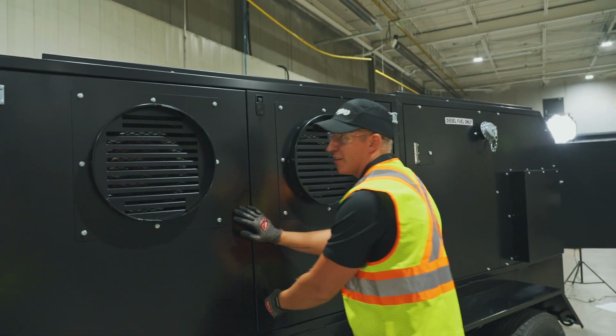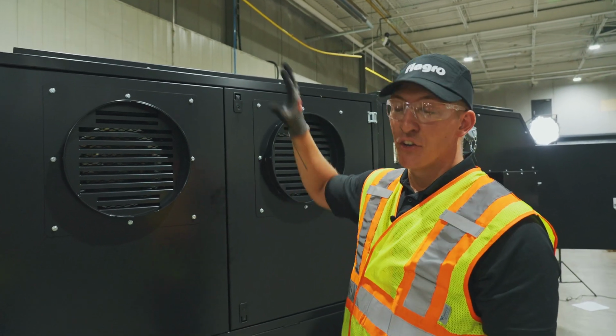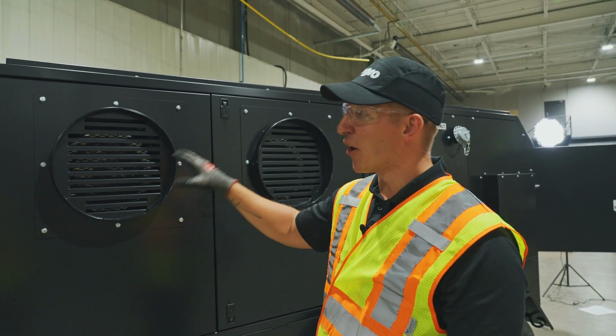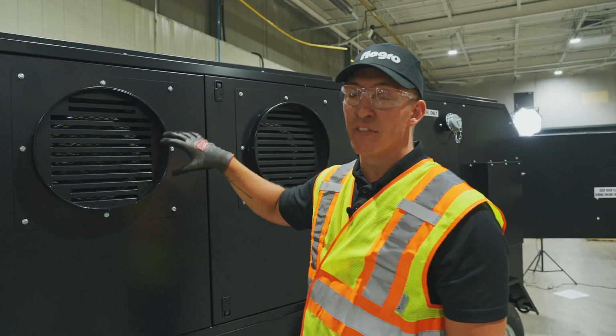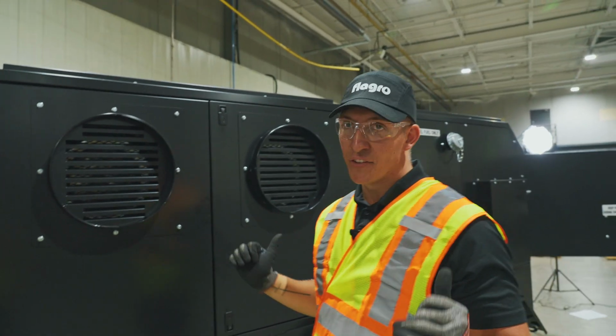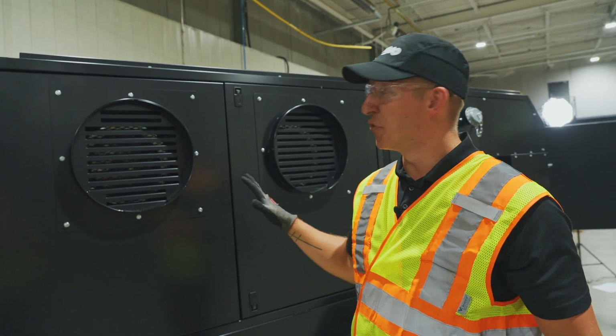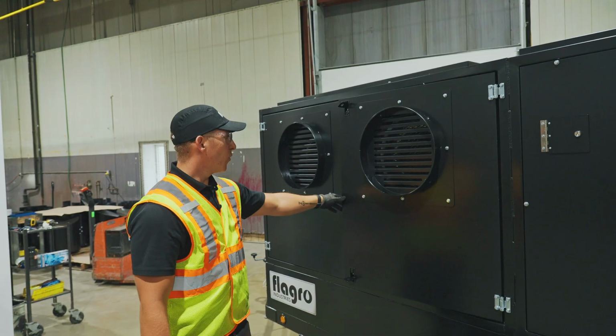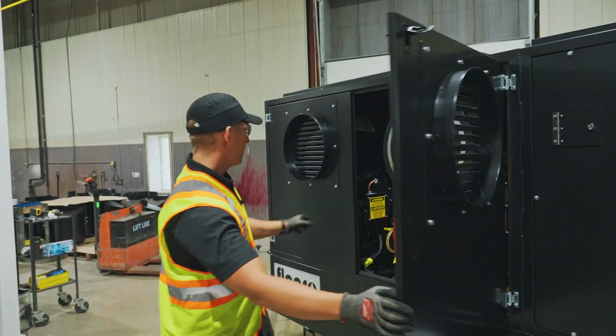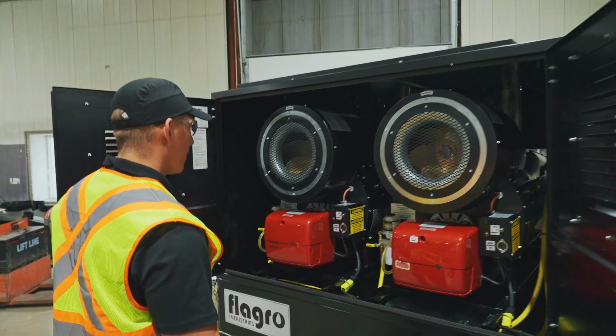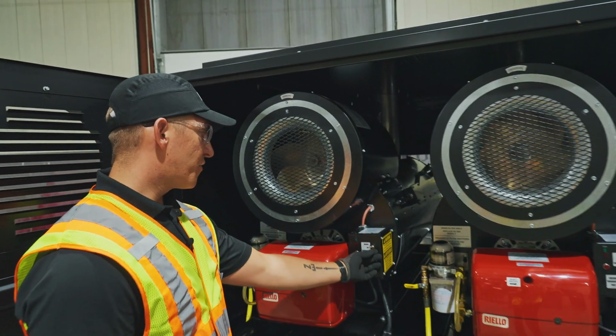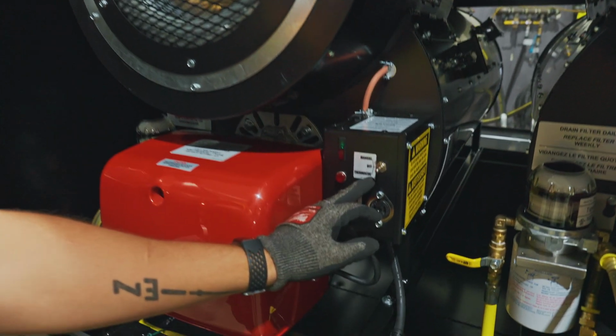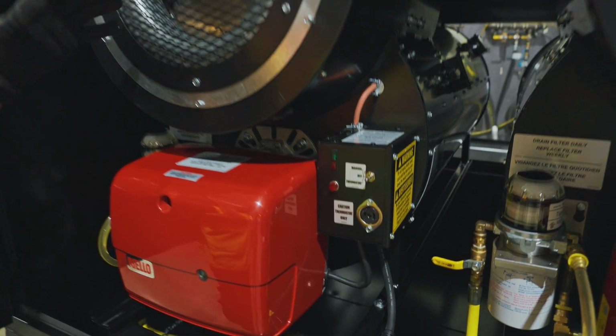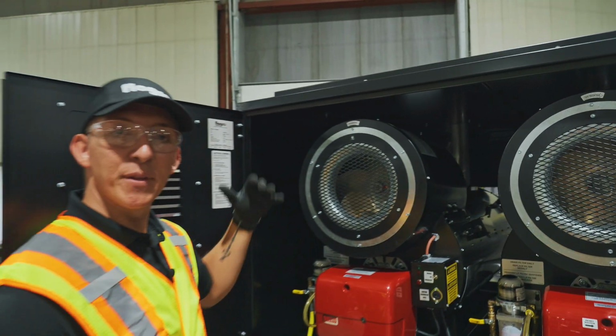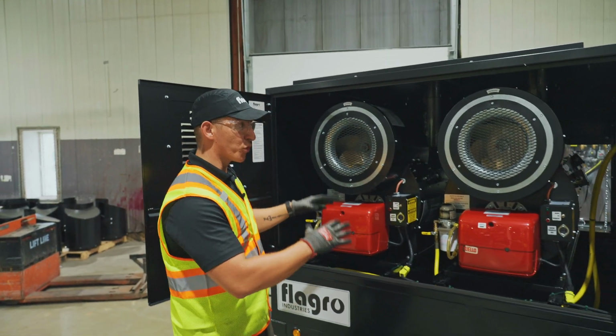During operation, you will need to leave your outlet doors open. You can hook up ductwork on that side to the outlet of the heaters, but like I had said previously, if you close that door, the kill switch will turn everything off at that point. When you're ready to turn the heaters off, open your inlet doors again. Turn these toggle switches to their center position off, and the heater will turn off, but the fan will continue running just for a cool down.